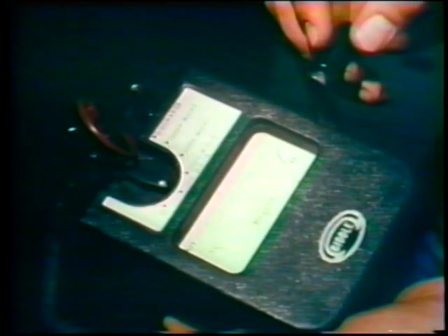After the electrician is sure the controller is de-energized, he tests the controller for grounds. The instrument this electrician uses is a megohm meter. A megohm meter is an instrument that measures high resistance and is used for checking insulation resistance. The electrician could use a multimeter or an ohm meter to test for grounds.